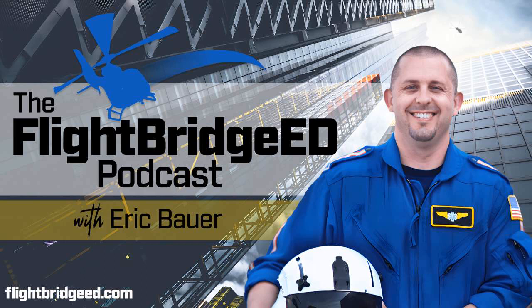An important side note, especially if you have referring cath labs where you pick up patients and bring them to larger centers: the manufacturer encourages people to initially put the device on autoflow when they put it in. It tends to decrease their cognitive load as they're working in the cath lab. What it does is automatically adjust the power level to maintain flow, but at the 3-hour mark it will immediately go up to P9. So if you're with the patient or loading them around that 3-hour mark and everything looks fine, then suddenly you get a bunch of alarms, you'll need to troubleshoot the device because it just kicked into high gear on you.